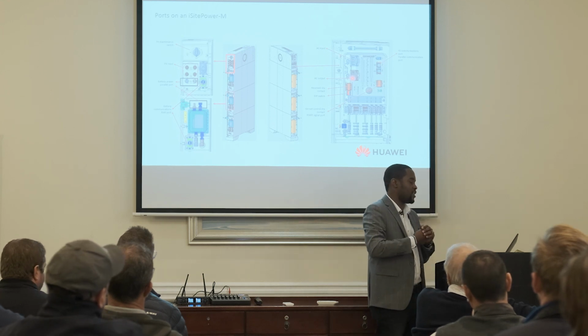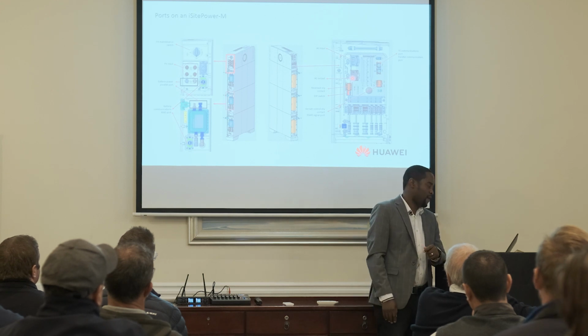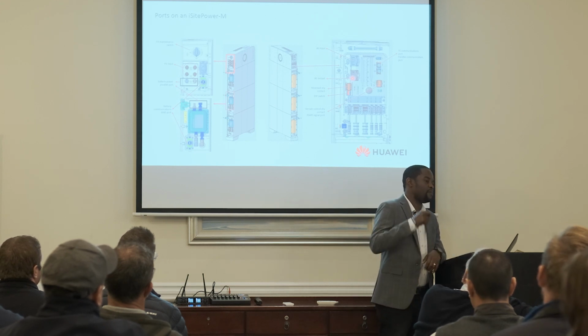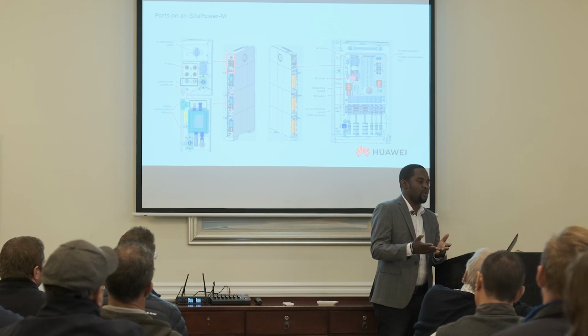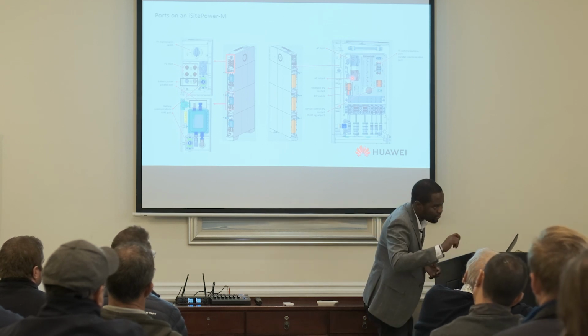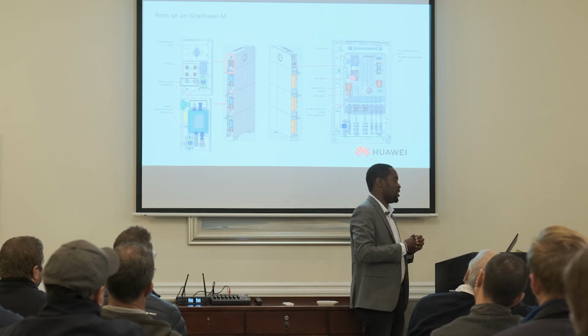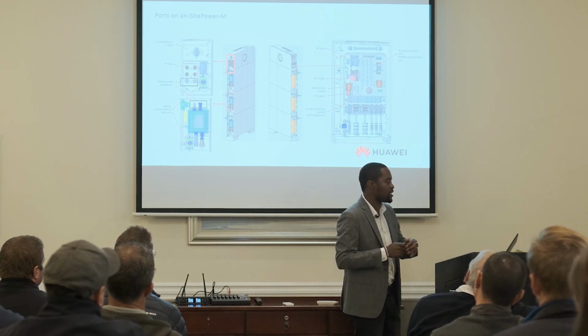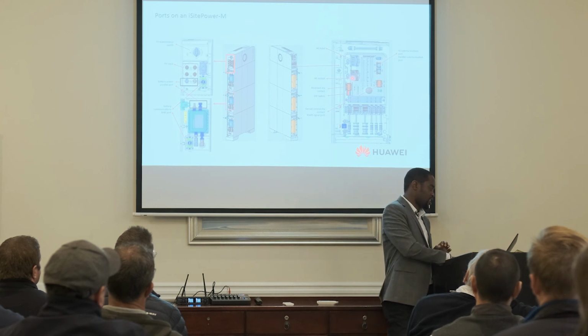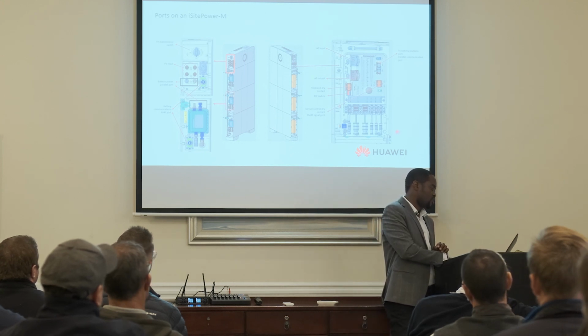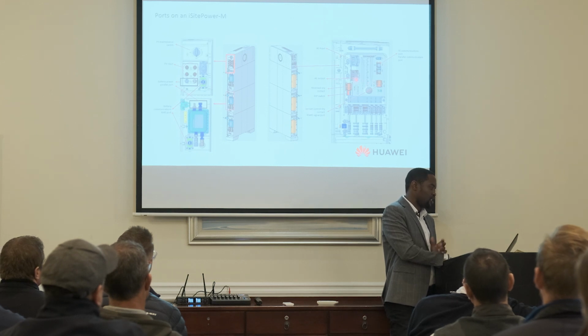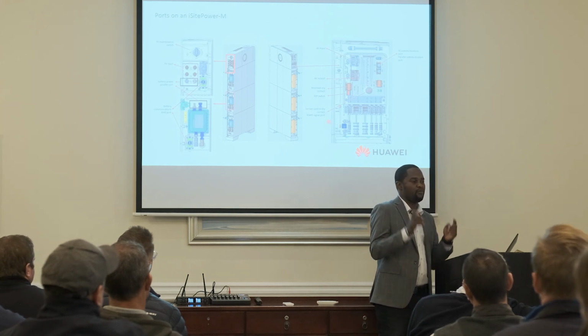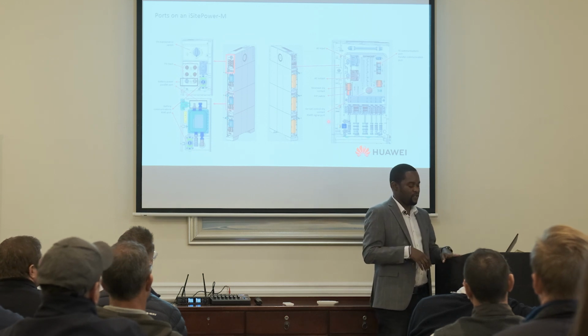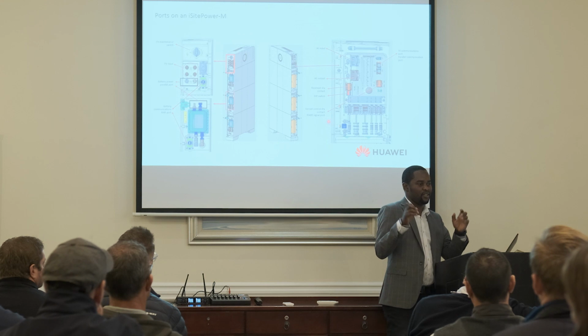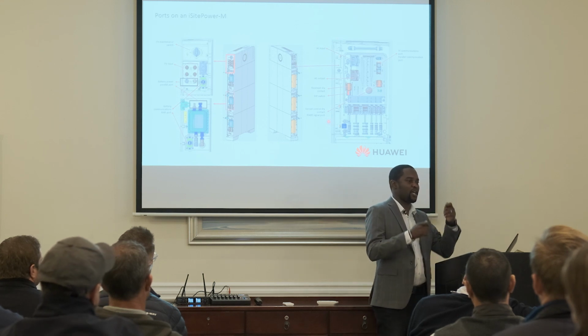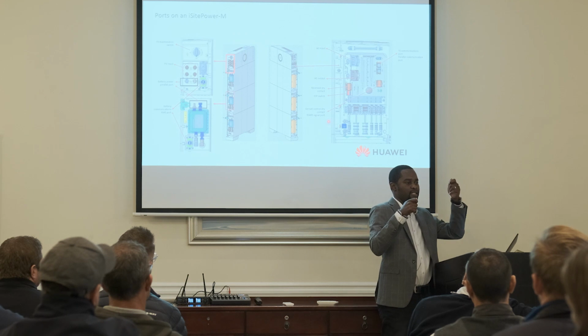Then when you are satisfied that your terminals are tight and the integrity of your terminations is fine, you can plug it into the inverter. So this also gives you extra room to work. Rather than coming close to the inverter when you're terminating, you take it out, then you terminate when you've got all the space and you are free, then you plug it in when you know that the terminations are tight and there's no loose connection. Then you've got the AC output, the same thing, you plug it out. On site, we used to call it idiot proof. You can't actually interchange the AC in and the AC out.